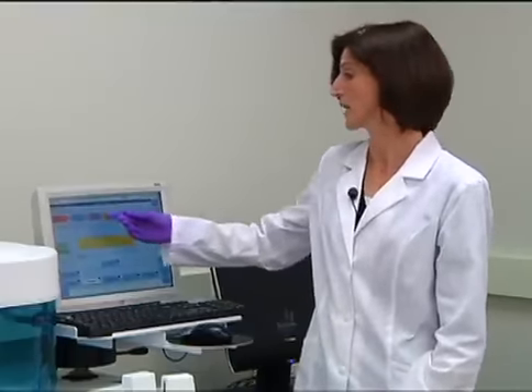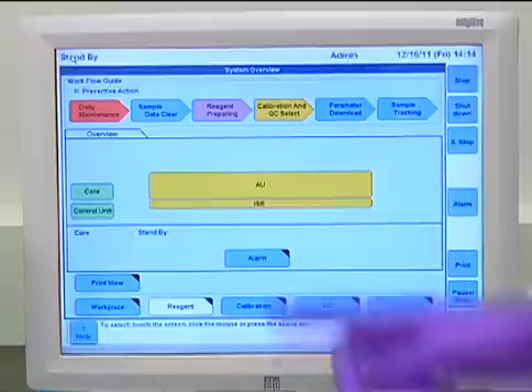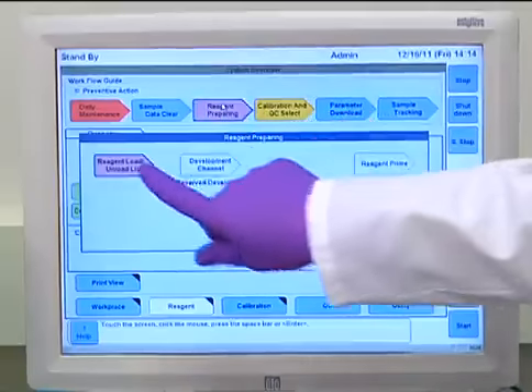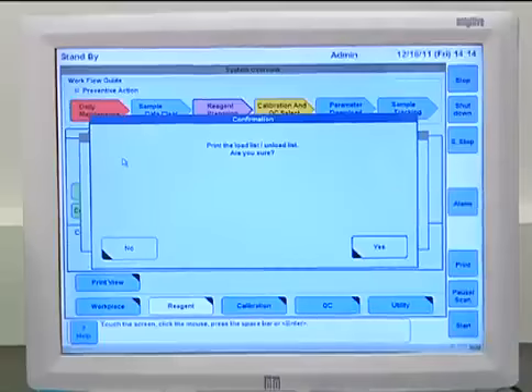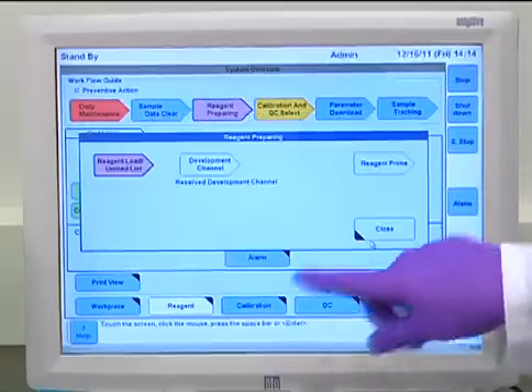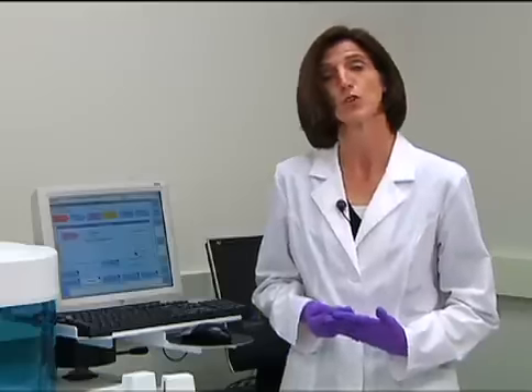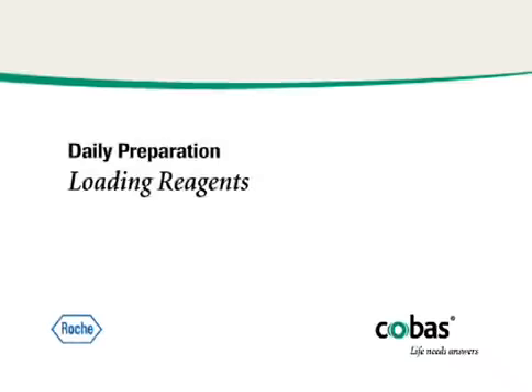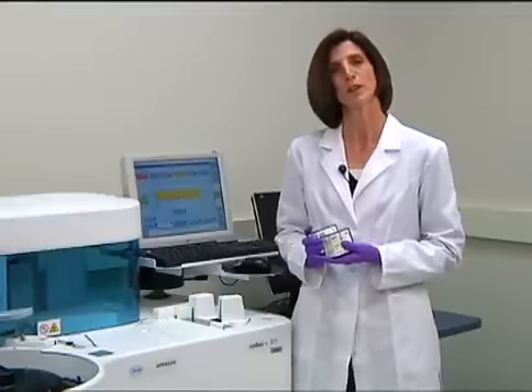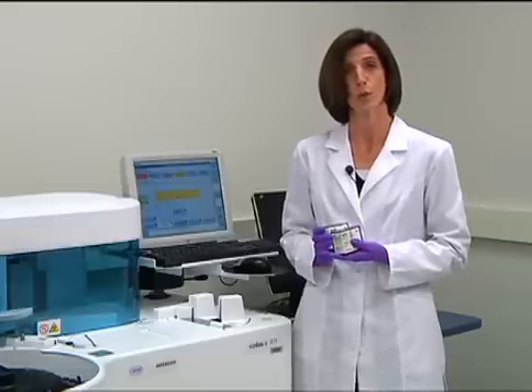So now we're back at the system overview screen, and you can see my reagent preparing button is purple. So what I'm going to do is select that, and that will allow me to generate a reagent load list. And on that load list, it will show me what reagent packs need to be loaded, what ISE reagents need to be loaded, and if any detergents also need to be loaded. So using that list, I can go and gather the materials that I need. According to my load list, I need to load 2 cobas C packs.